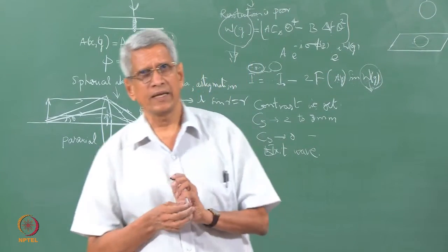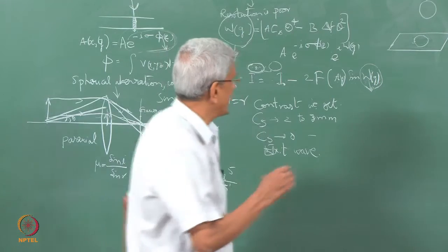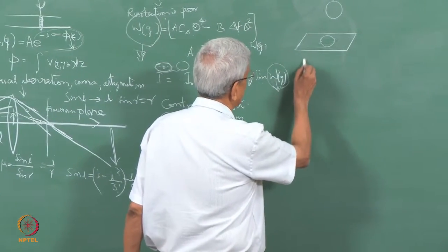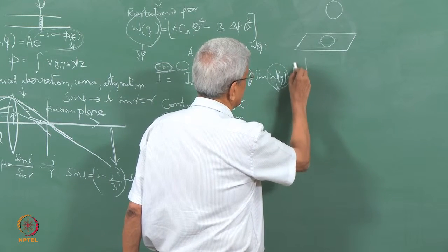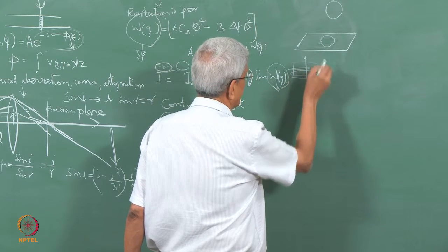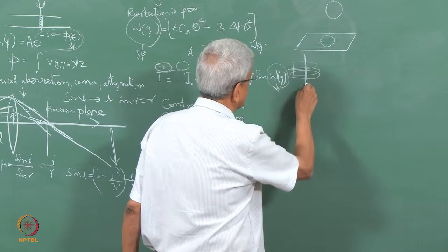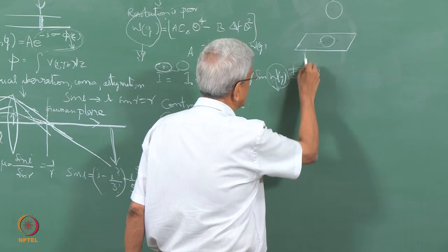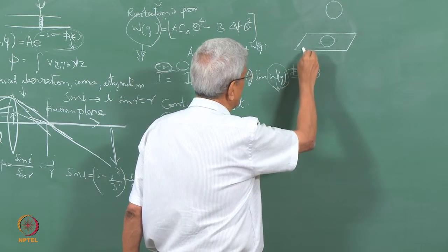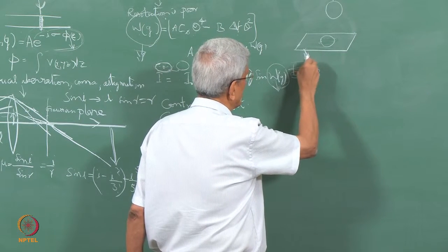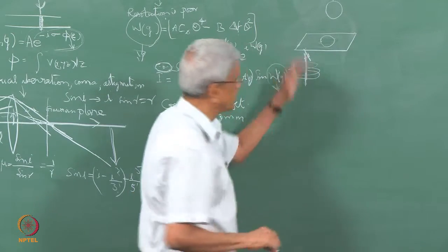In an electromagnetic lens, a current is passed through a coil, which generates a magnetic field. This is the coil current, and the magnetic field generated has a north and a south pole along that axis. As the electron beam travels in the same direction along this optic axis, it is undeviated. But if the beam is inclined with respect to the axis of that field, then the Lorentz force will be acting on it.